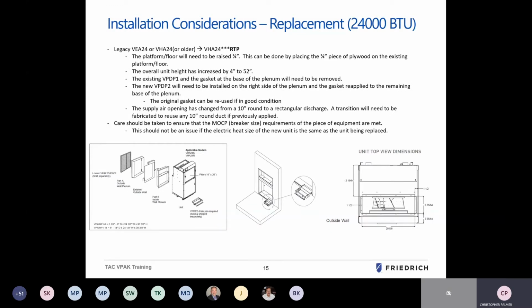Now here on the legacy VEA-24 or the VHA-24 or older, converting to a VHA-24 RTP. The platform in this case needs to be raised 3/4 of an inch. It is recommended to use a 3/4 inch piece of plywood. However, some local codes don't accept plywood as an alternative. So other sources of alternative supporting may have to be based on local code requirements. You should check with your local code requirements and your inspectors more directly and what they are willing to accept. So that is something to be considered here in the future. But our recommendation is that a 3/4 inch piece of plywood be used on the existing floor to raise up the platform, and that should be adequate enough for the installation.